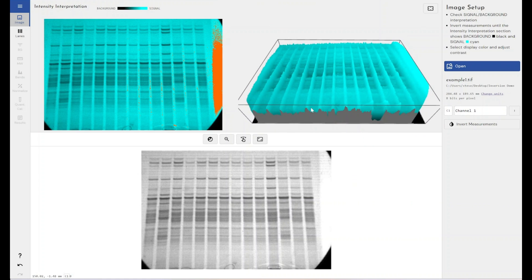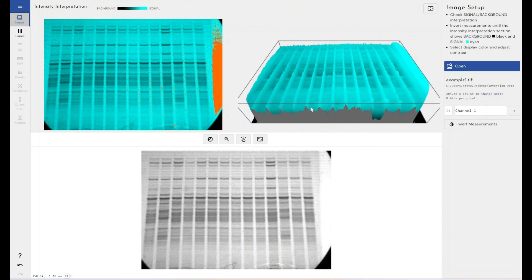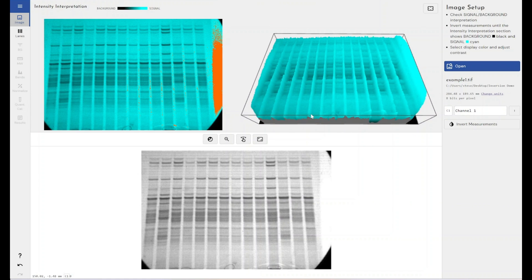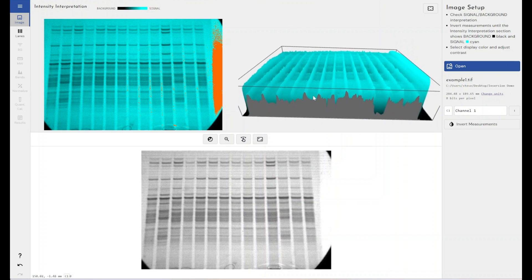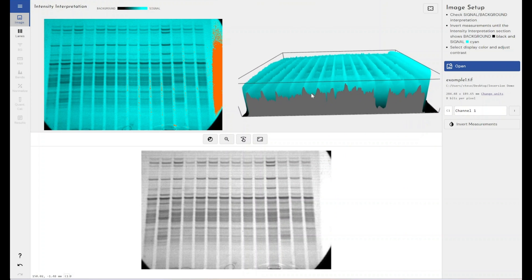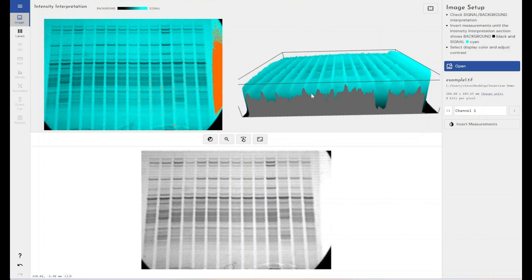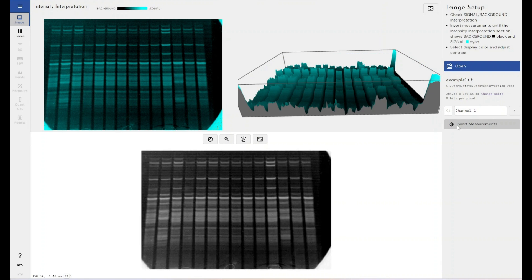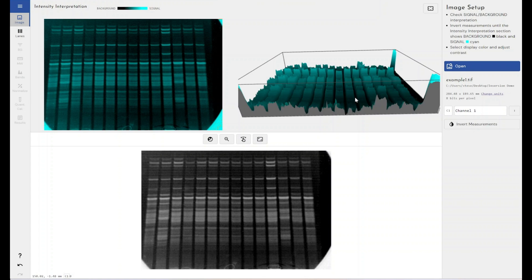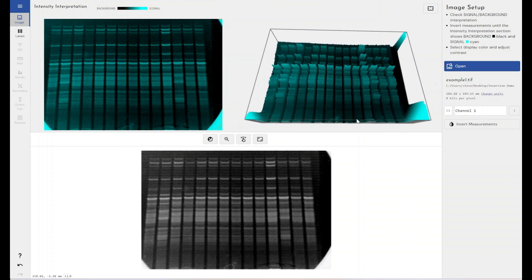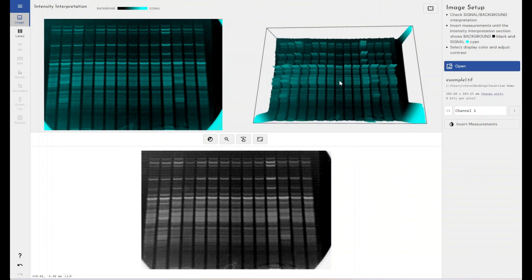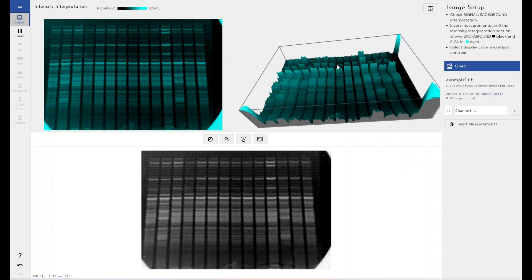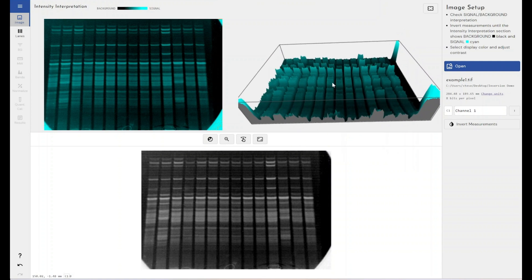Our data here in the image, our bands are actually showing as troughs instead of peaks, and we need them to be displaying as peaks because it makes the whole process a lot more accurate and feeds into all of the clever algorithms that we have for automatic lane detection and things like that. So we've got this button which inverts the measurements. If I click on this, you can see that I've now inverted my measurements. My bands are now showing up as peaks, which is lovely, fantastic. However, this has inverted the color of the image, so now we've got white bands on a black background.